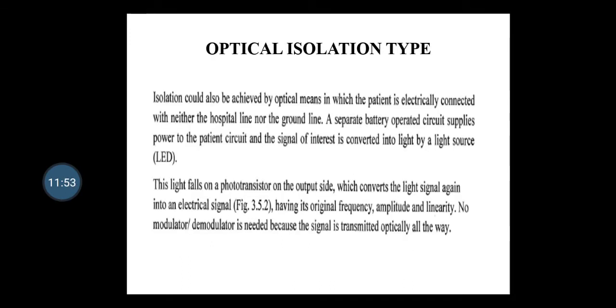Then another one is optical isolation. Instead of a primary transformer circuit, we provide isolation through optical means. Isolation could also be achieved optically, in which the patient is electrically connected with neither the hospital line nor the ground line. A separate battery operated circuit supplies power to the patient's circuit, and the signal of interest is converted into light by an LED light source.